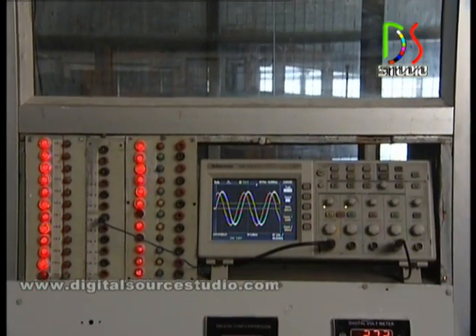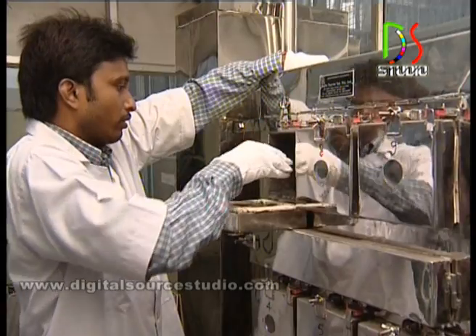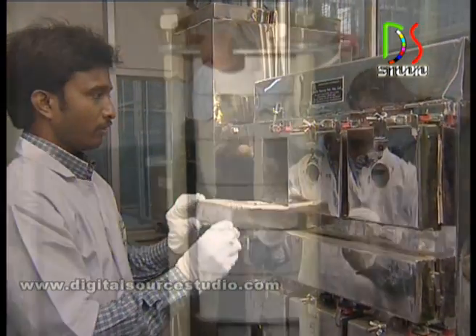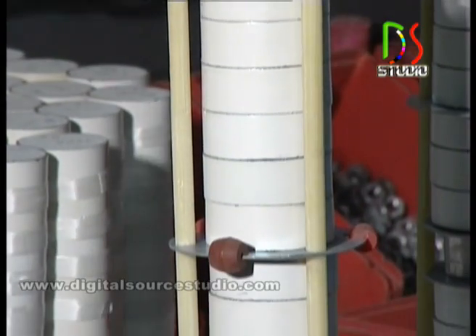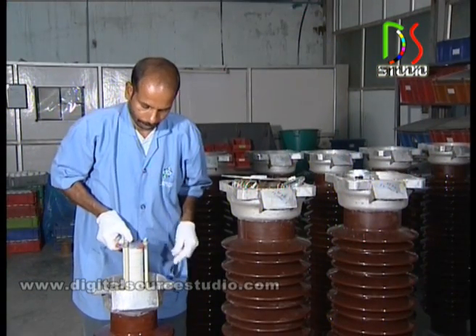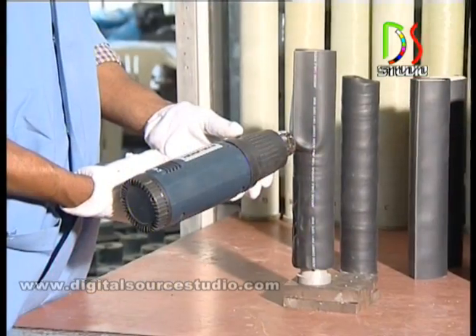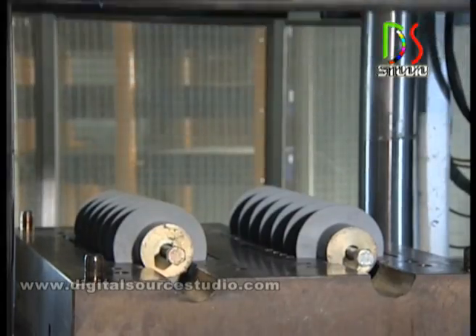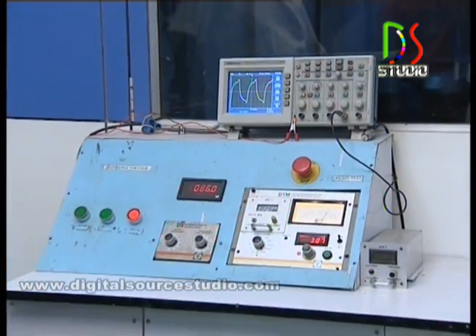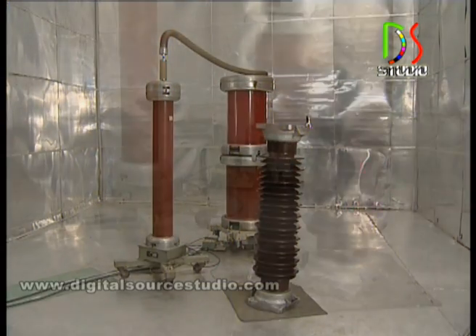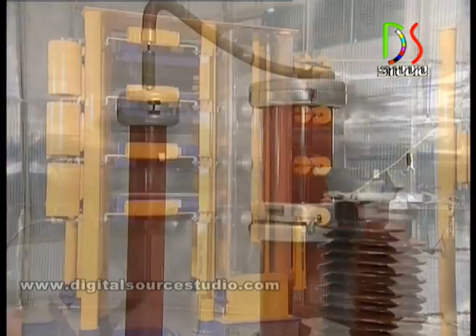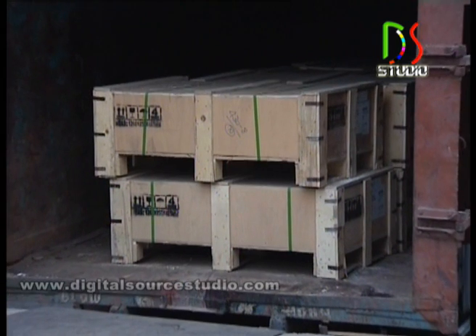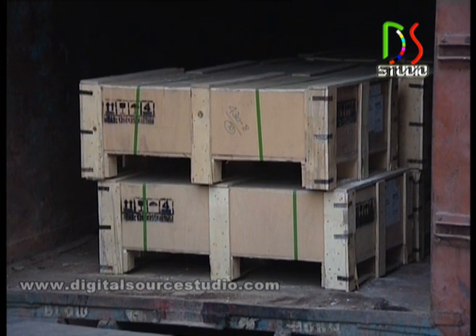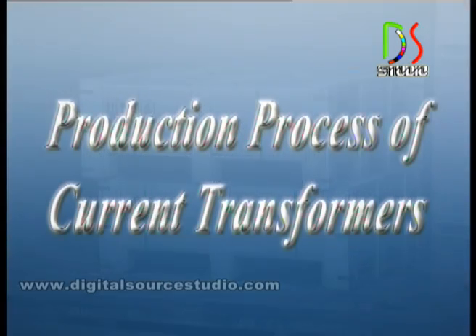Then some sample blocks, as per the laid out procedure, are subjected to type tests as per IEC standards. Then these tested blocks are stacked rating-wise and assembled into specified porcelain insulators, molded with silicon rubber. Then the finished arresters are subjected to electrical routine tests as per IEC standards: reference voltage test, partial discharge test, residual discharge voltage test. Then the arresters are fixed with nameplates, packed carefully and transported to respective destinations.